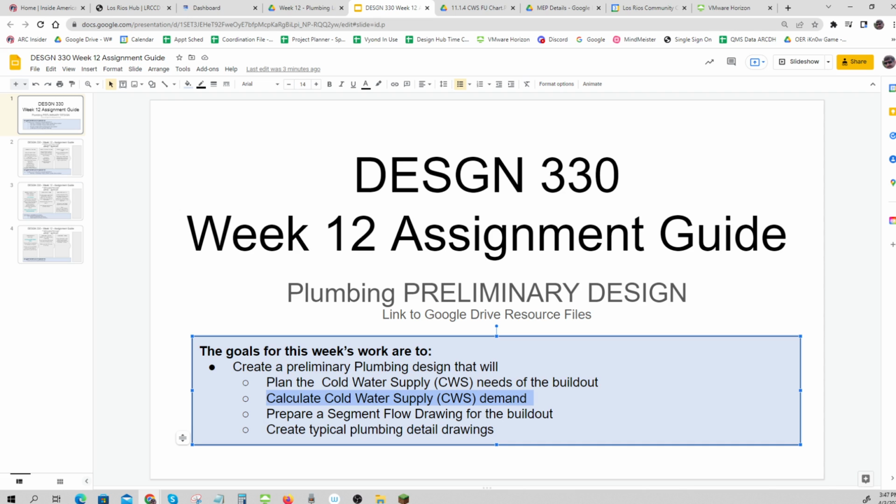Okay, a shower head in California is supposed to deliver no more than 2 gallons per minute when it's fully open and you have full pressure in your building. Okay, and so those are all designed. So we're going to make a calculation of how much water we would have when each item is fully open.